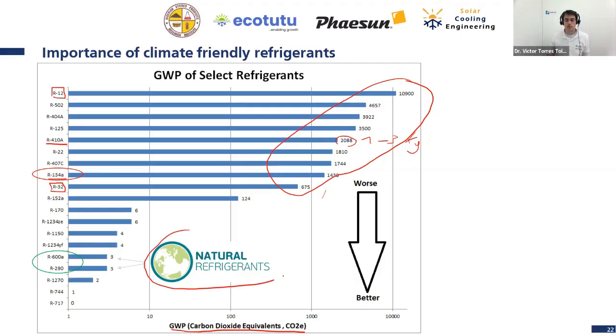What is a natural refrigerant? It's a refrigerant that is in nature. It's not a chemical. And we, for example, use here R600A and R290. This is isobutane and this is propane. They have a very low global warming potential. So it doesn't matter if this refrigerant comes to the atmosphere, because the impact on climate is very low.